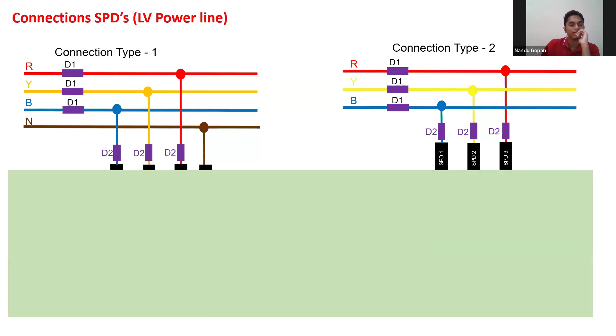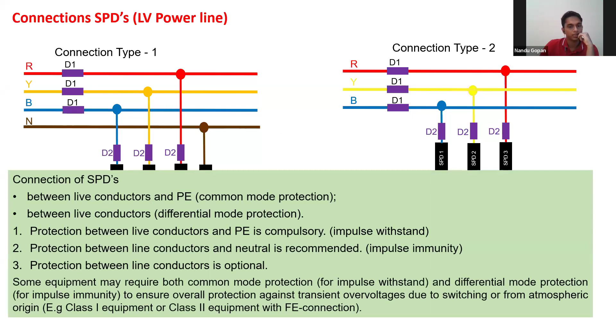Yes. So if anyone is asking about common mode and differential mode protection, yes, SPD will be doing that. Common mode protection means between live conductor and PE conductor. Differential mode means between live conductors. Since there is an SPD here, if there is a potential difference between this line and this line, all the SPDs will be working to give an equal potential. I'll explain in the next slides. So SPDs will give common mode and differential mode protection.